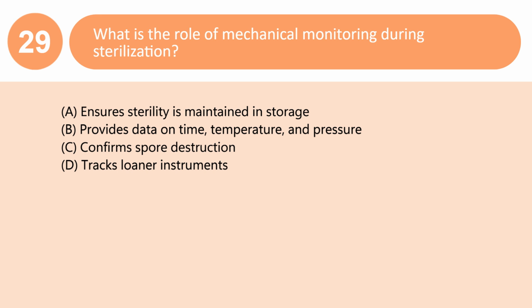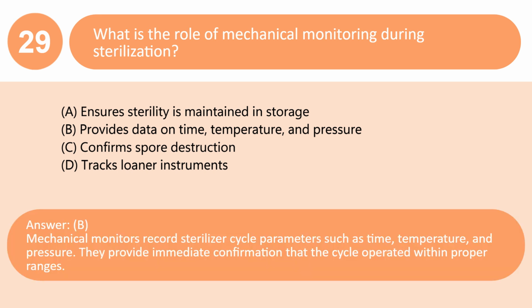What is the role of mechanical monitoring during sterilization? A. Ensures sterility is maintained in storage. B. Provides data on time, temperature, and pressure. C. Confirms spore destruction. D. Tracks loaner instruments. Answer: B. Mechanical monitors record sterilizer cycle parameters such as time, temperature, and pressure. They provide immediate confirmation that the cycle operated within proper ranges.